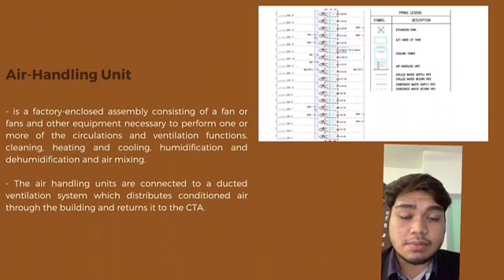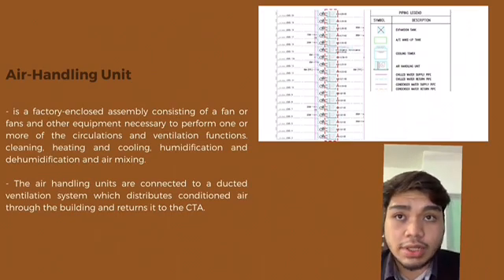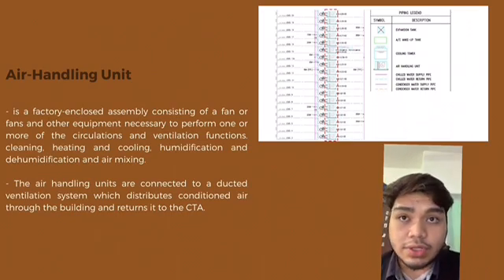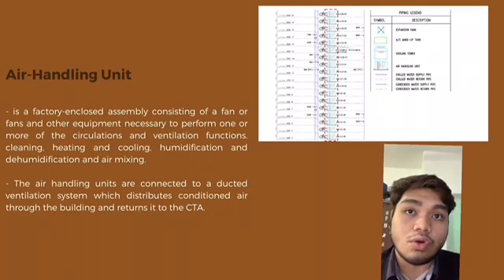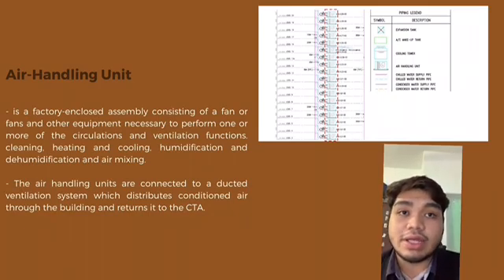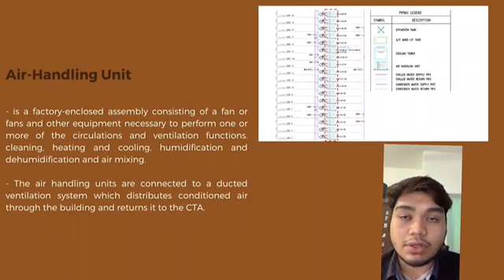Mechanical ventilation system used in the Pinnacle Sunway building. The first one is the air handling unit. According to ANSI or AHRI, an air handling unit (AHU) is a factory enclosed assembly consisting of a fan or fans and other equipment necessary to perform one or more of the circulation and ventilation functions: cleaning, heating and cooling, humidification and dehumidification, and air mixing.